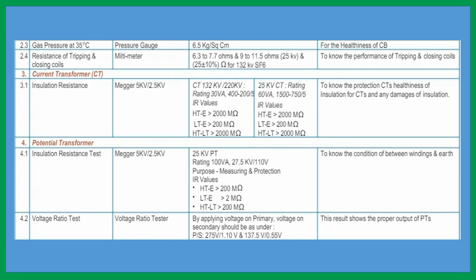Then gas pressure at 35 degrees centigrade at the pressure gauge is 6.5 kg per square centimeter for the healthiness of the circuit breaker. Oh, this is for the circuit breaker. Some portion has not come. Resistance of tripping and closing coils is 6.3 to 7.7 ohms and 9 to 11.5 ohms for 25 kV, and 25 plus or minus 10% ohm for 132 kV SF6 circuit breaker.